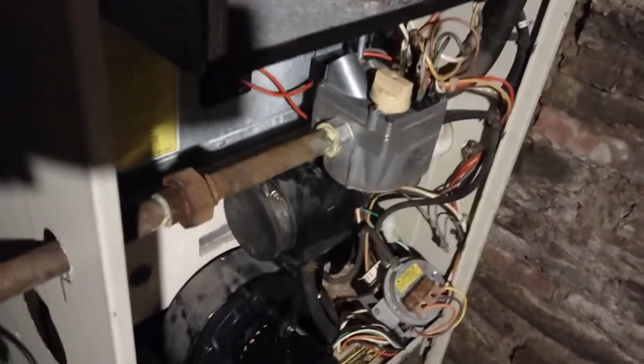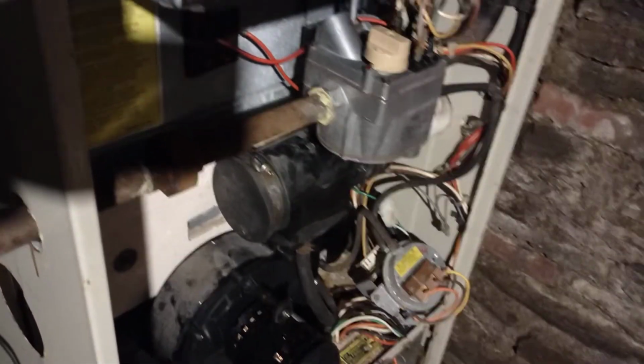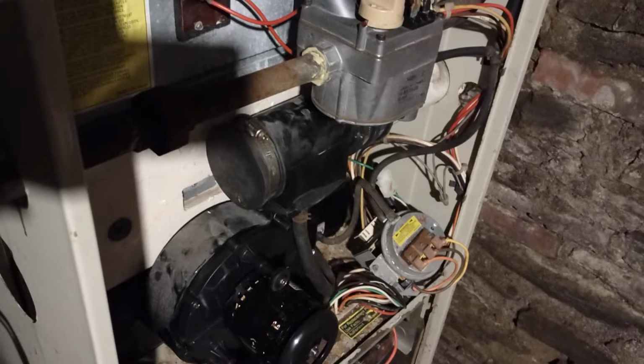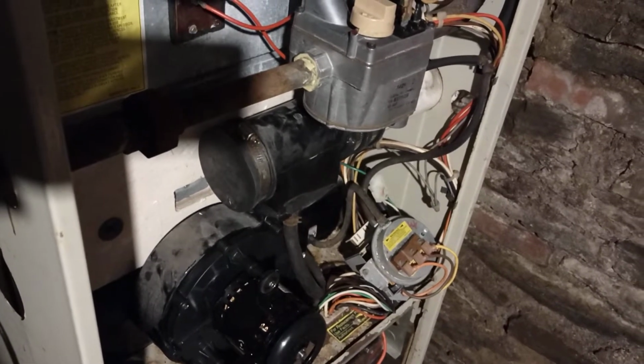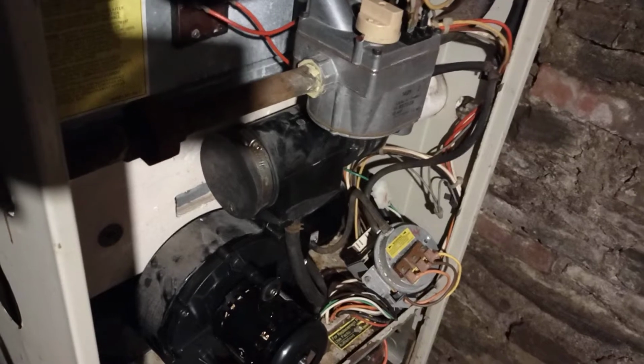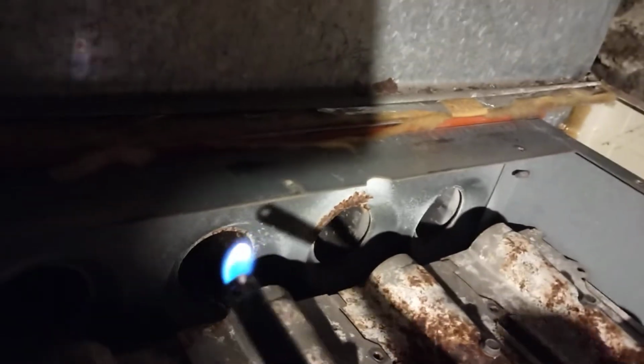Now, as far as the heat exchanger goes, yes, that is a concern. Why get into this thing if the whole heat exchanger, the central element of the furnace, is no good? So we decided to have a look at that first and see if we could test it. Here's your heat exchanger. And what we did, to test it before we put all money into it, was to take a flame and stick it inside of each tube.